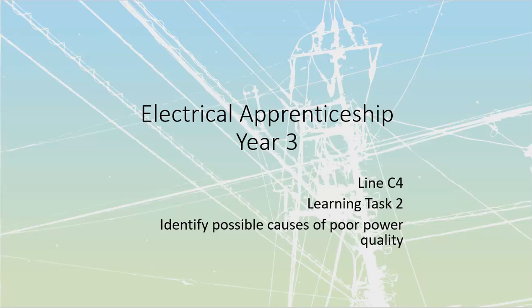Tree branches can cause line-to-line or line-to-ground shorts. Animals contacting the equipment can also cause line-to-line or line-to-ground faults, even bird strikes on top of a transformer. The transformer cans themselves can be shorted, since they're tied to ground, so we can short to ground whenever a bird or squirrel runs across there.